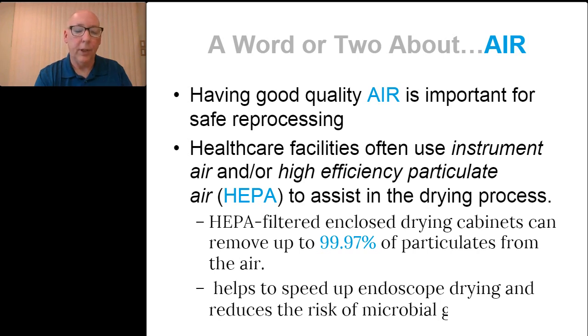The pre-filter is in place to act as the first line of defense to filter particulates in the air. I can't stress enough a couple of things relative to those filters. Follow your drying cabinet's IFU, the instructions for use, for appropriate filter replacement intervals. That filter may not be completely obvious to you on a regular basis. Check your manuals for where it's located, find out where it is, and then act accordingly based on your drying cabinet IFU relative to replacement intervals for those filters. If you aren't familiar, then again, refer to your user manual and/or contact your drying cabinet manufacturer for further information.